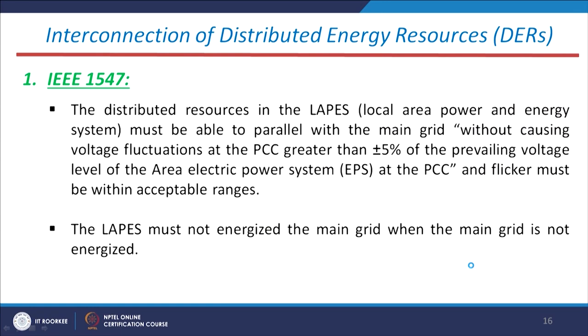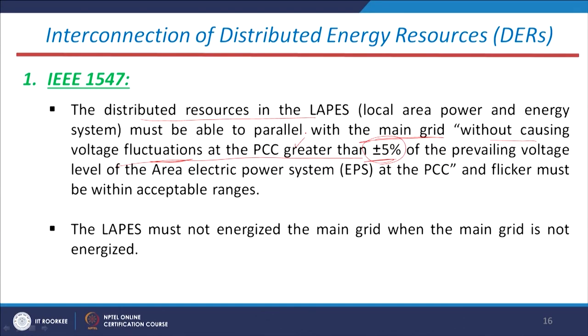The distributed energy sources in the LAPES must be able to operate in parallel with the main grid without causing voltage fluctuations at the PCC greater than plus or minus 5 percent. So when connecting DERs such as solar or wind to the existing grid, voltage fluctuations at the PCC bus should not exceed ±5 percent of the nominal value — this is one of the standards of the IEEE 1547 series.